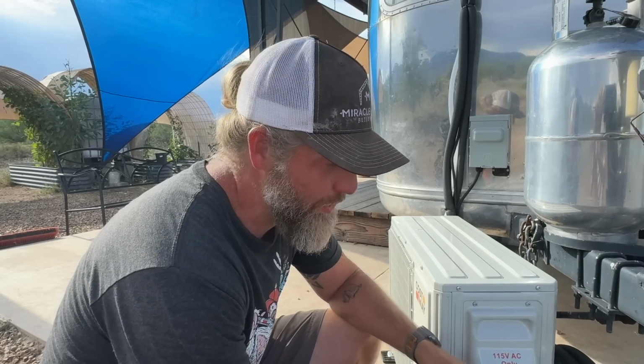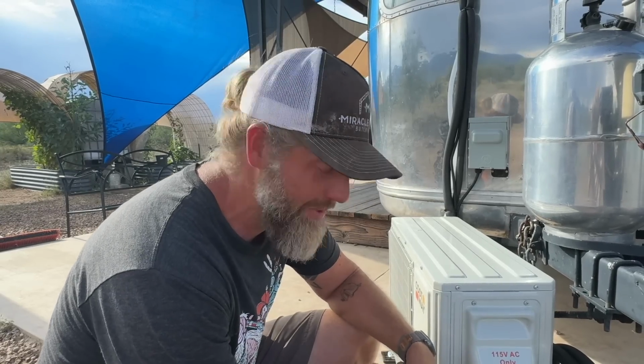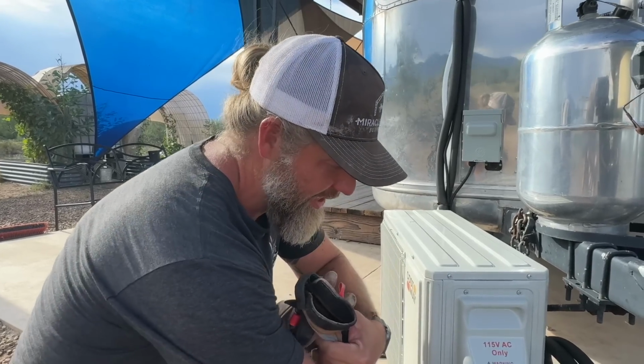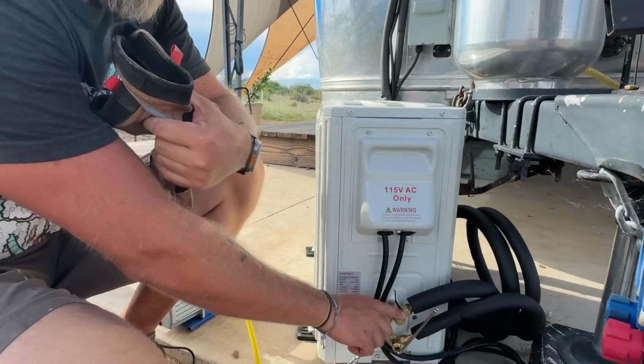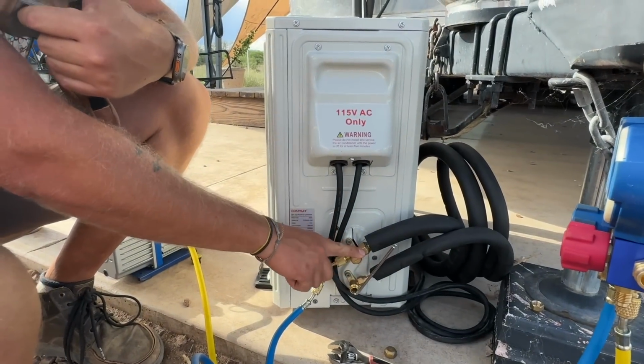No leaks as far as we can tell, the pressure has held exactly the same. So the next step is to release all of the liquid, then take the service port off here and release all of the gas, and then we can go turn the unit on inside and test it out.